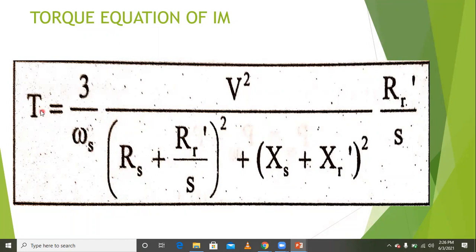In the torque equation, torque is proportional to V squared. Based on this, by controlling the voltage, the torque of the induction motor is controlled and consequently the speed of the induction motor is controlled.